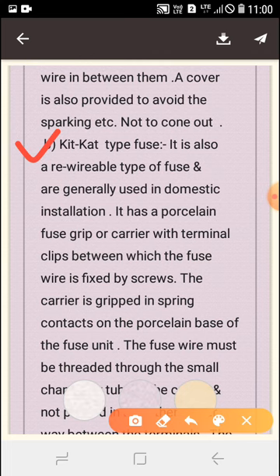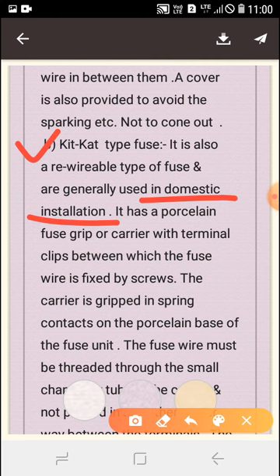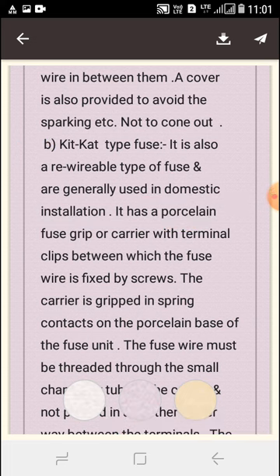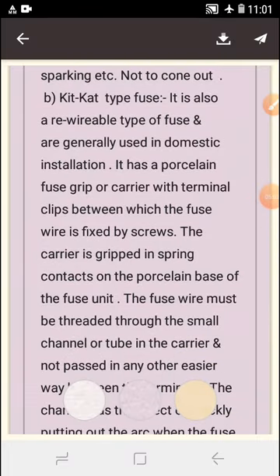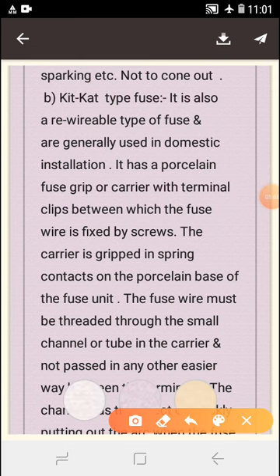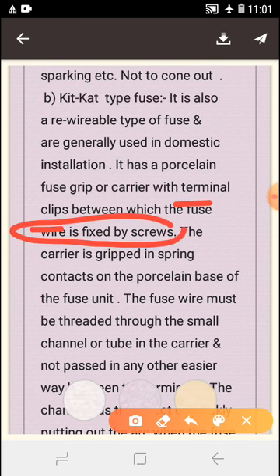The kitkat type fuse is also a re-wireable type of fuse and is generally used in domestic installations. It has a porcelain fuse grip or carrier with terminal clips between which the fuse wire is fixed by screw. The carrier is gripped in spring contacts on the porcelain base of the fuse unit.